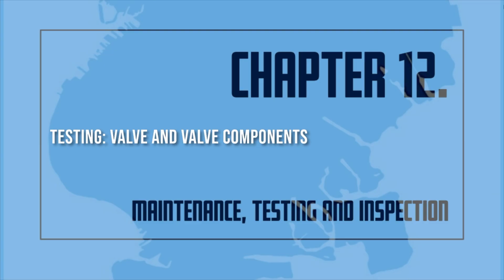Each dry pipe valve shall be trip tested annually during warm weather. It should be tested in the spring to allow time before the onset of cold weather for all water that has entered the system or condensation to drain to low points or back to the valve. Every 3 years and whenever the system is altered, the dry pipe valve shall be trip tested with the control valve fully open and the quick opening device in service.